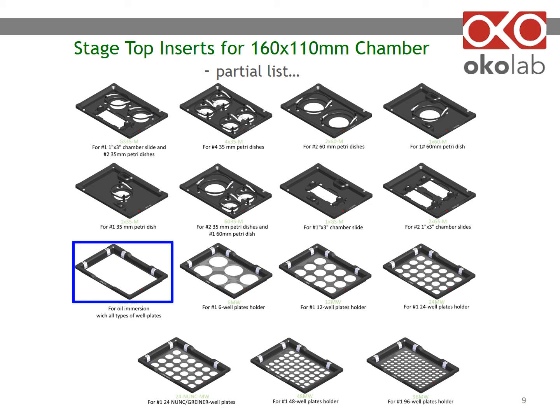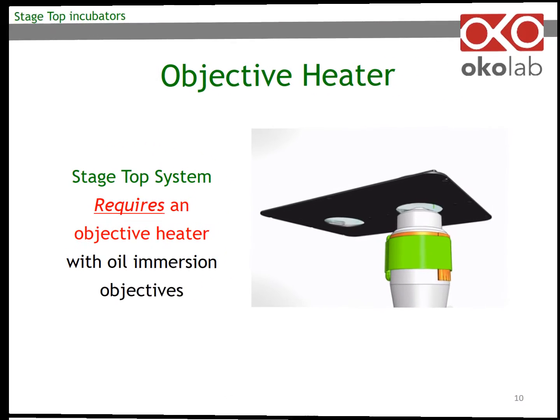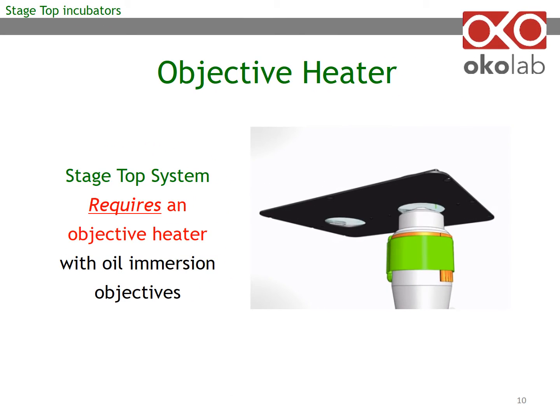This will allow the objective to move freely between wells. If you are using an oil immersion objective, you have to use an objective heater. The objective heater is represented by a heating band, secured around the objective. An oil immersion objective will touch the bottom of the well through the oil and will draw heat away from your sample — this is why an objective heater is required with oil immersion objectives.